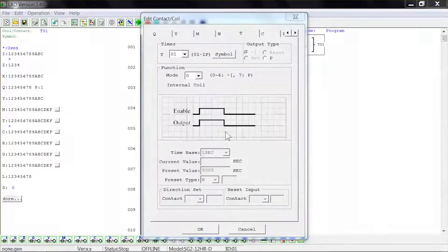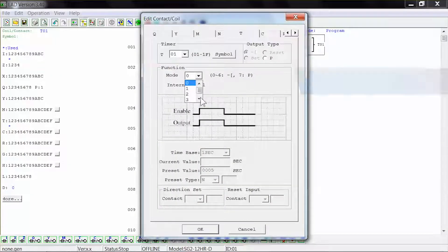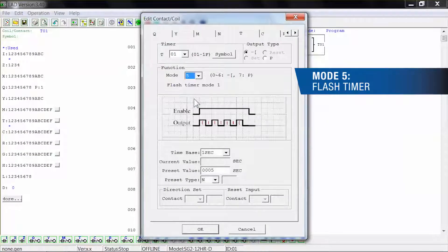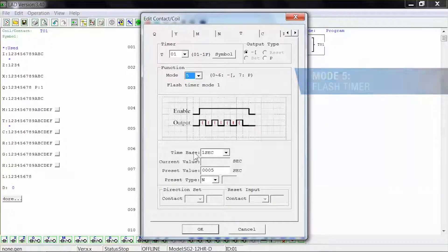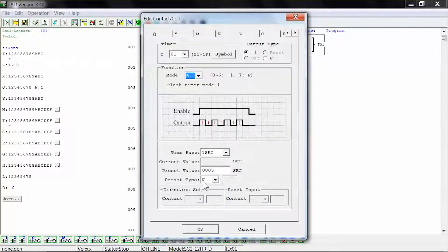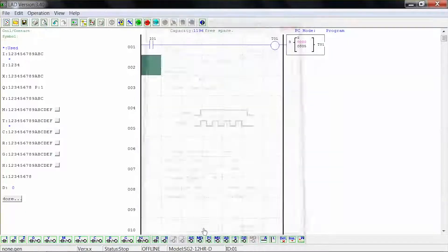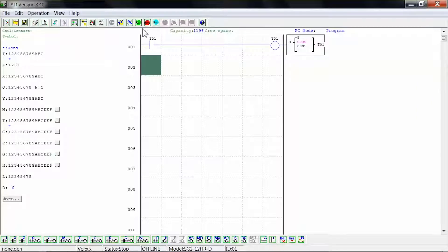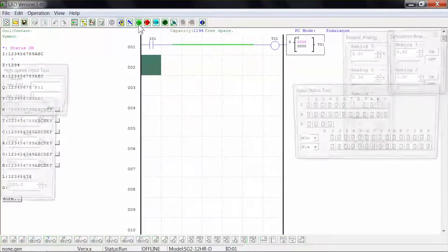For this example, select function mode number 5, which is a flash timer version 1. Select time base for 1 second, preset value for 5 seconds shown as 0005, and preset type of N for numeric constant. Click OK to close the window and click run to start the simulation.